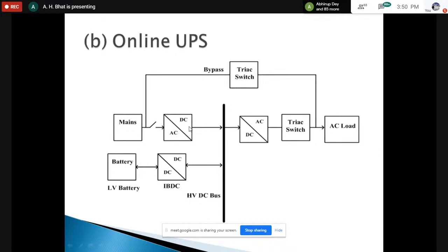It is converted into DC, so this is our high voltage DC bus, and then the inverter converts this DC into AC and feeds the AC load. Simultaneously, what happens? This power flows in this direction. Whatever power is coming from the mains, a part of that flows in this direction, and with the help of this bidirectional isolated DC to DC converter, or DAB, the power is stored in the battery bank.